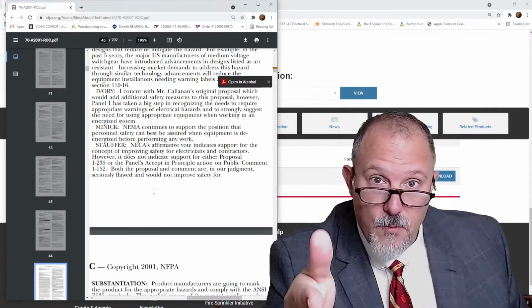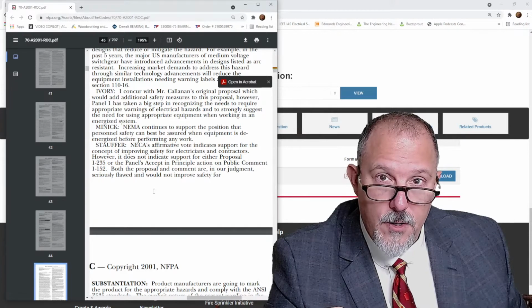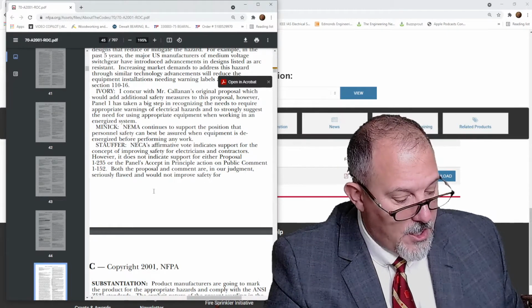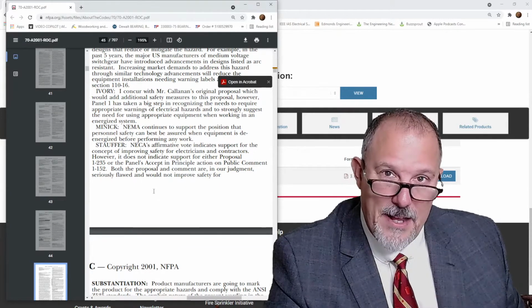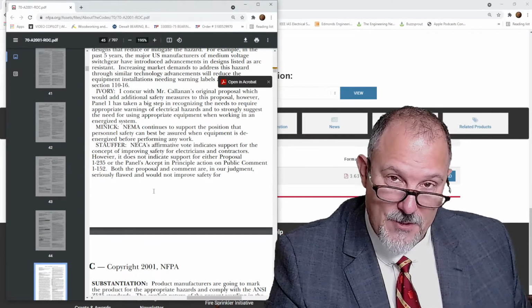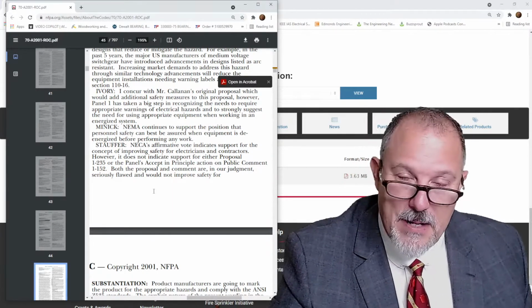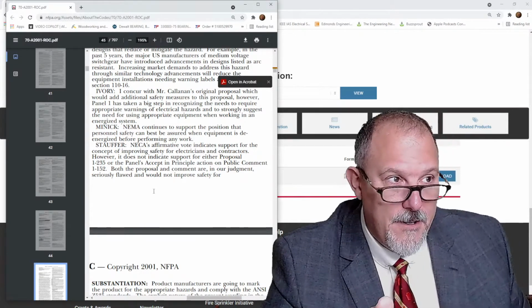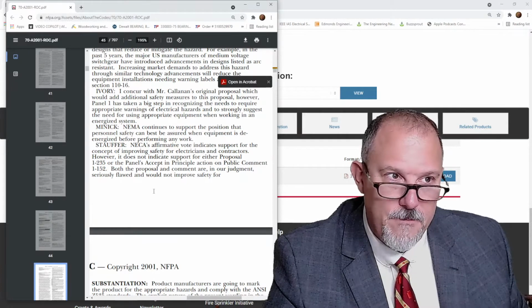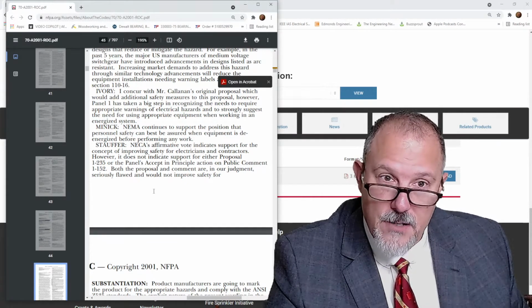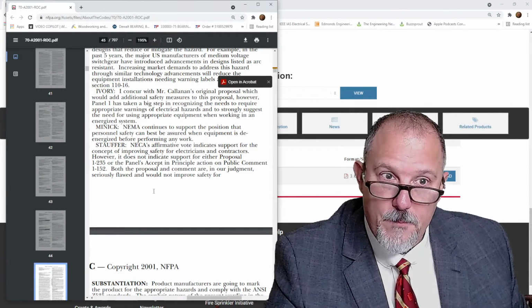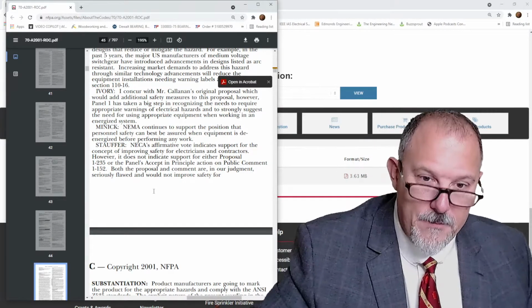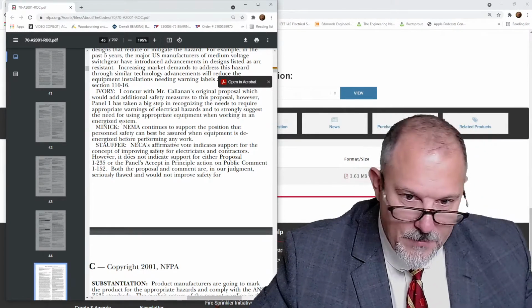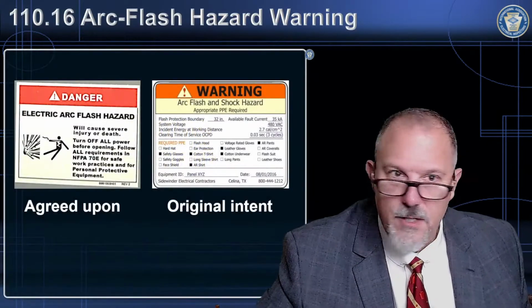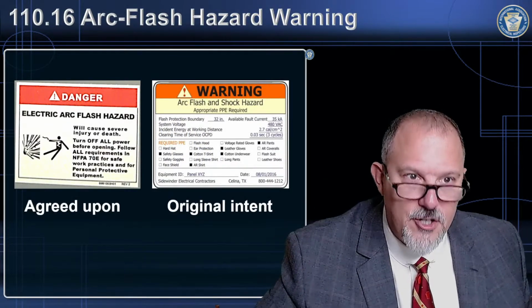So, and that's solely on the burden of the inspector. Think about it. There's nothing in the code that defines likely to require energized, likely to require to be examined or adjusted while energized. This is a relationship between the installation, the engineer, the owner, and the inspector to determine what is and isn't likely. But in reality, we're talking about a very simple label change, which is the one you see farthest from me, an electric arc flash hazard.